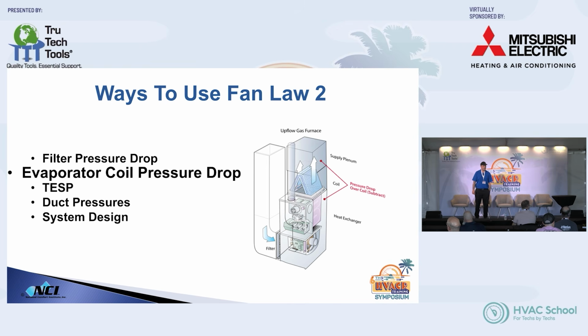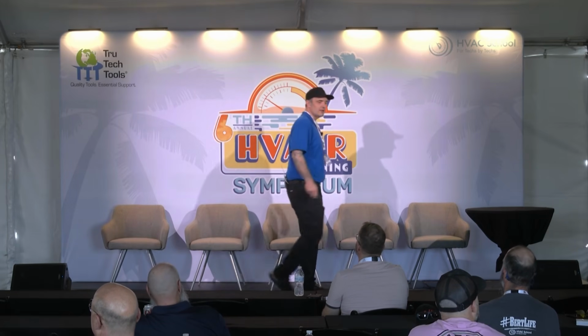So our evaporator coil pressure drop. This is another fun one. Do you guys all look at rated pressure drop for evaporator coils? Do you look at the numbers? I always thought it was like a knee pad that came with the box, you know? You try to keep something clean, you put your sandwich on it at lunchtime. But there's actually numbers in there that you could use, which is pretty cool.